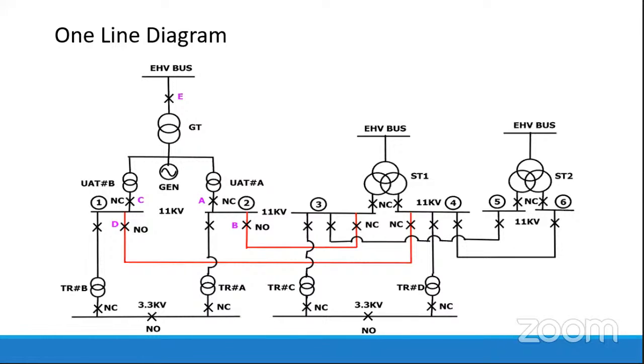So normally we can say this scheme is a two incomer, one bus coupler scheme, where the two incomer feeders will be in line and the bus coupler will be open. And if any one of the incomers gets isolated, then the bus coupler will be in line. So we can say it's an N-1 contingency of this network.